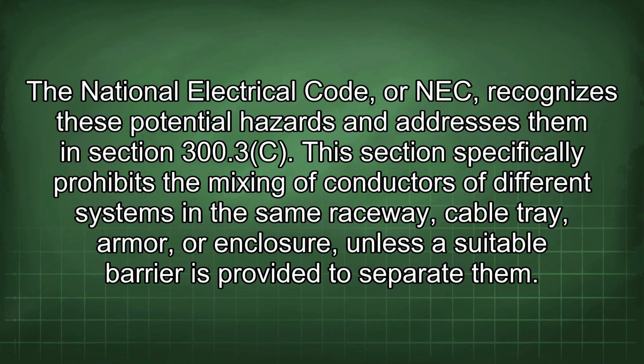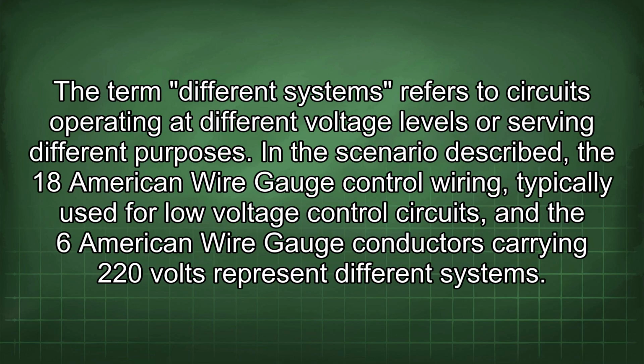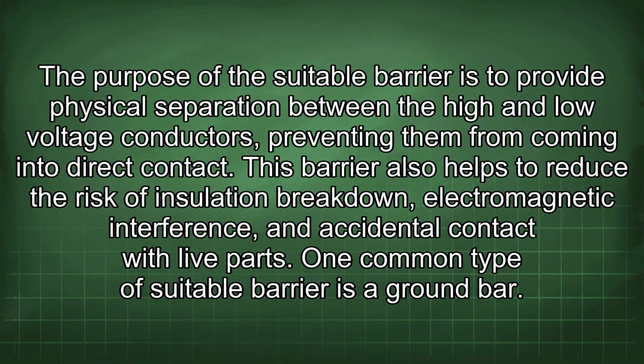This section specifically prohibits the mixing of conductors of different systems in the same raceway, cable tray, armor, or enclosure unless a suitable barrier is provided to separate them. The term different systems refers to circuits operating at different voltage levels or serving different purposes. In the scenario described, the 18 American wire gauge control wiring, typically used for low voltage control circuits, and the 6 American wire gauge conductors carrying 220 volts represent different systems. The purpose of the suitable barrier is to provide physical separation between the high and low voltage conductors, preventing them from coming into direct contact. This barrier also helps to reduce the risk of insulation breakdown, electromagnetic interference, and accidental contact with live parts.